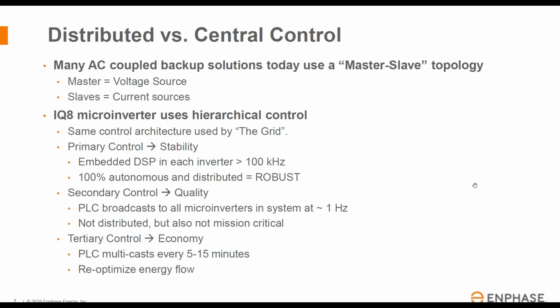So it's using the same wiring within the facility that is used for moving the power. We're also using that same wiring and cabling for the communication, and that's occurring at about 1 hertz. It's not distributed. That is starting to be centralized control. However, it's also not mission critical. So if there's a communication interruption, the system doesn't fail because the primary control will continue to keep the system stable even in absence of a secondary control signal.